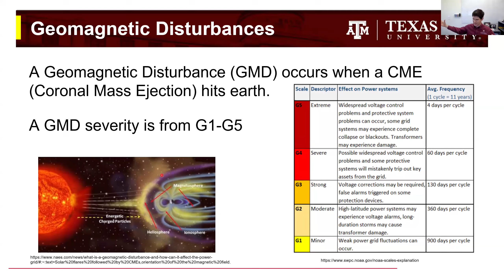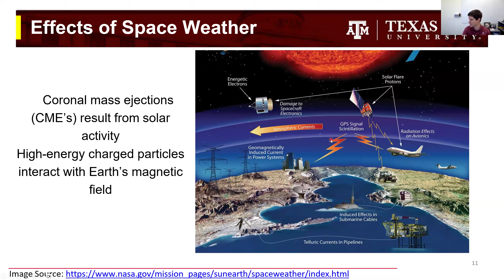Those changes can cause problems. We're most familiar with the problems caused to the electric grid, where we have GICs in our power system, but space weather also impacts more than just the electric grid. It can impact spacecraft electronics if they're not shielded properly, and it can affect GPS by disrupting signals, which impacts aviation, communication, and potentially PMUs. If severe enough, it can also affect undersea cables and cause currents flowing in pipelines, similar to GICs, and if cathodic protection isn't proper, that can cause issues too.